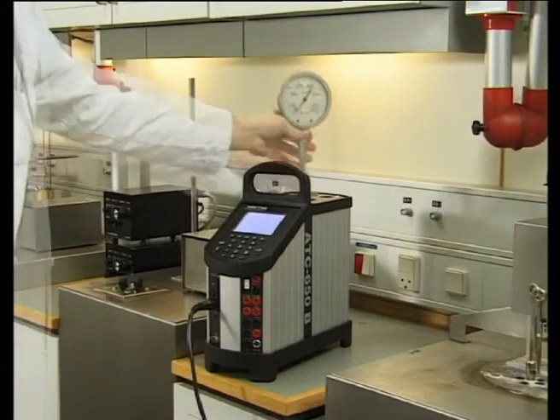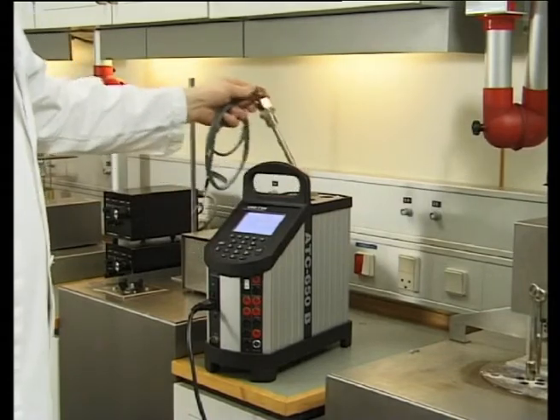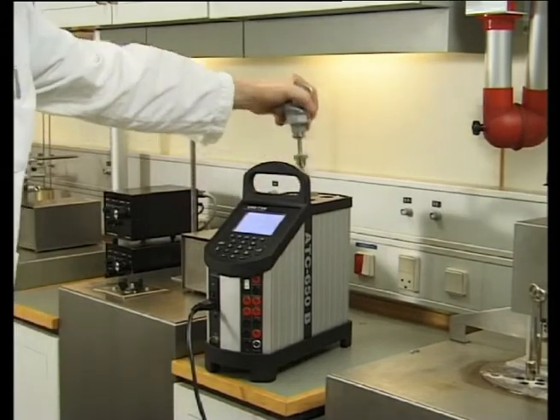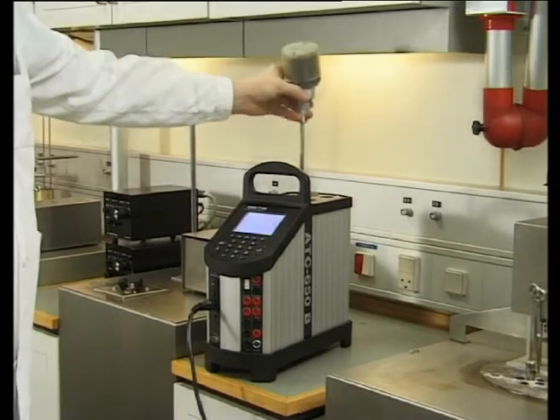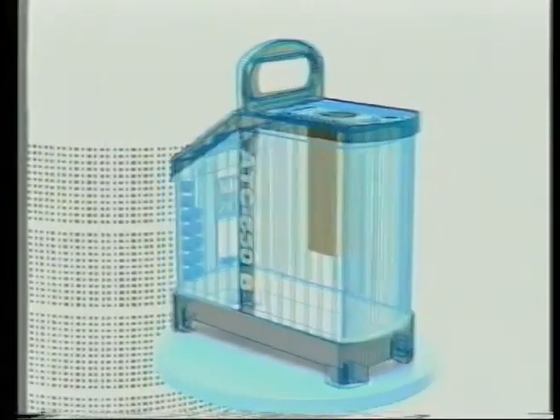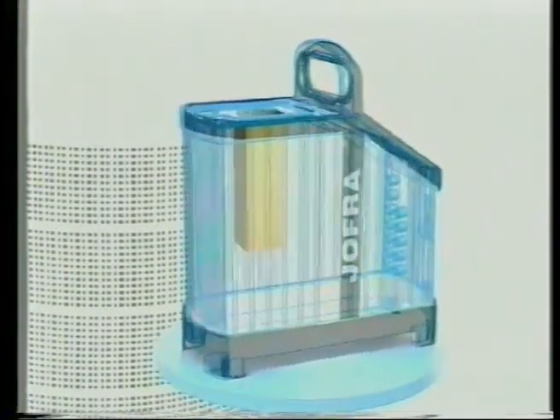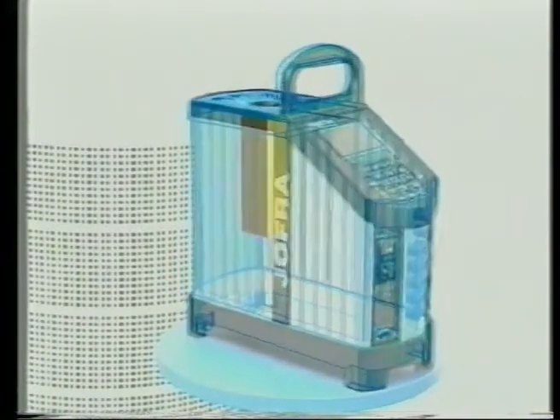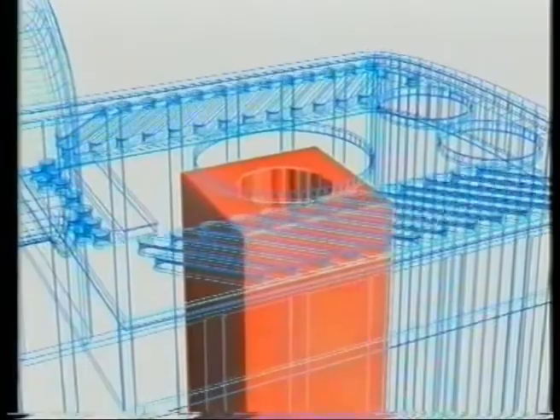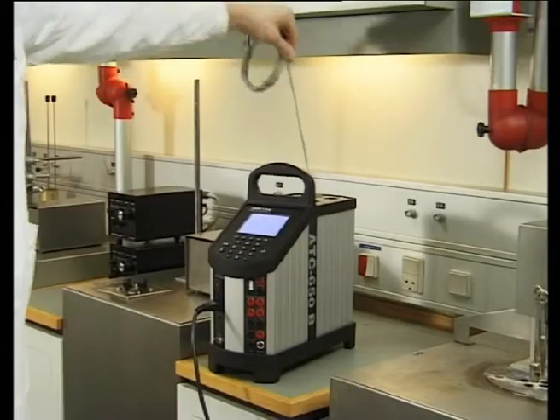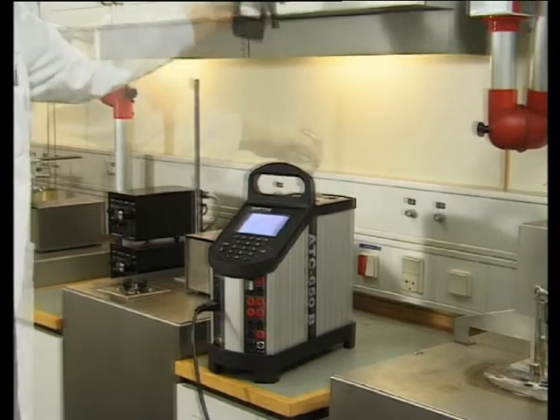The construction of the ATC series means that you can now calibrate many different types of sensors, including liquid-filled and large mechanical sensors. The heating element is constructed in two zones. Each is independently controlled. The homogeneity in the active part of the heating element is close to that of a laboratory liquid bath. The lower region ensures optimal heat dissipation throughout the entire block, and the upper region compensates for heat transport from the sensor under test and from the top of the block. This design feature also eliminates the need for insulation of the sensor under test.